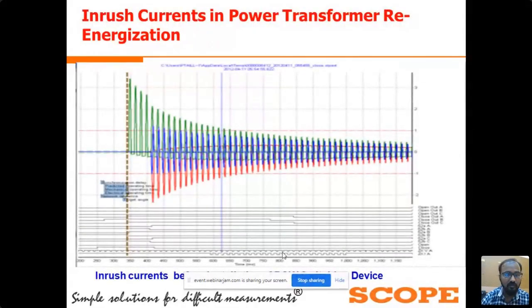Now we will see the actual waveform for power transformer switching. Here you can see the waveform with random switching, with random de-energization of the power transformer. Before this closing event, at the time when we opened the CB contacts, we don't know at what electrical angle the CB contacts get opened. So we don't know how much residual flux is available in the power transformer core.